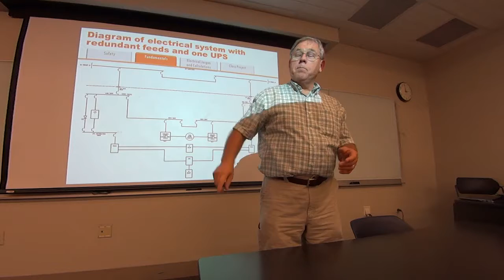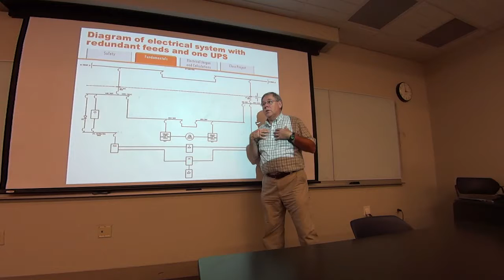I mean, if you do a data center, you're probably going to have most of your stuff underground except for this up here. This may be coming in overhead. You'll want to put a lot of surge protection right here. You definitely want it there. And they make these really nice MOV gizmos that you can put in here that can accommodate 250,000 amps. But we've never had, to my knowledge at Oak Ridge, we've never had a problem with surge. It's always been voltage dips that have caused problems, because of faults on lines and stuff like that. And we've had lightning strike buildings. I stood there and watched it, hit lightning protection.